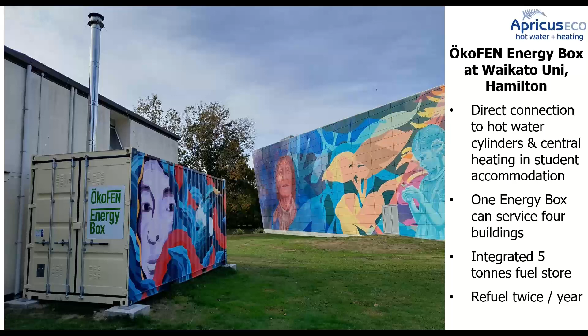So I'll get to your questions in a sec. The other way, as we start expanding, we can put a couple more in here. So now we've got 2 20-foot containers. We've got 256 kilowatts in this container, and we've got some fuel store in this container. And so we've got up to 107 megawatt hours of fuel stored in here, and they can be side by side, end to end, even stacked if you want to do it. You'd actually put the boilers on top of the fuel store because they're lighter than the fuel store, and then you'd have some steps going up to it, probably reverse it, put the steps on the back, as it were. A bit more cost, but if you're very space constrained or want to particularly have a vertical alignment, then that can be done.